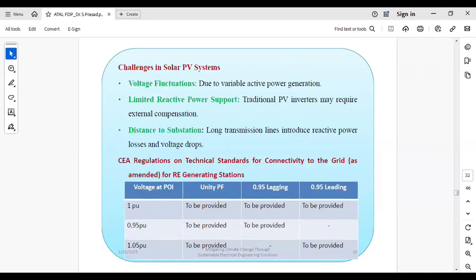So what exactly are we doing in this test? According to the CEA regulations, you can see this table, CEA regulations on technical standards for connectivity to the grid, for RE generating stations. RE generating means renewable energy generating station, the PV plant. When a PV plant is going to be connected to the grid, you have to follow these CEA regulations. That means the test you need to conduct is when the voltage at the POI is 1 per unit, and you have to provide unity power factor.